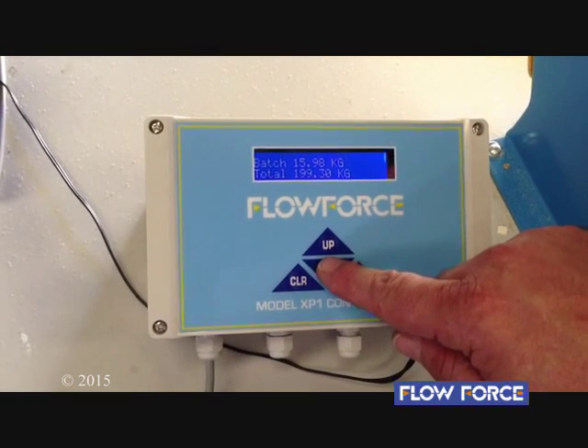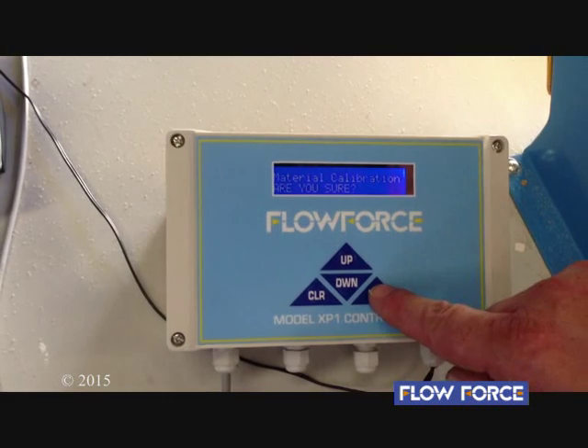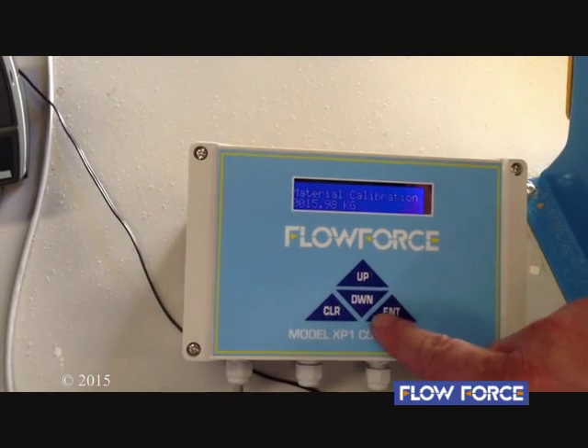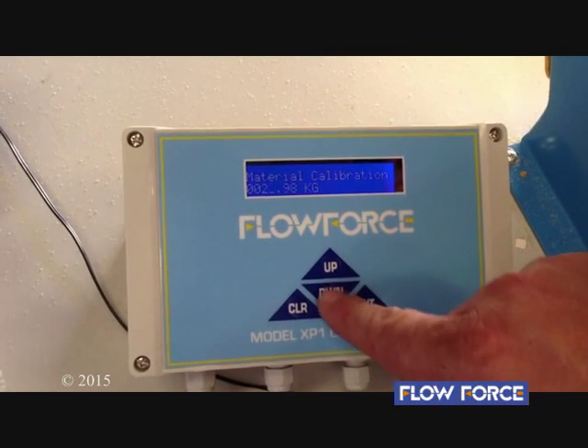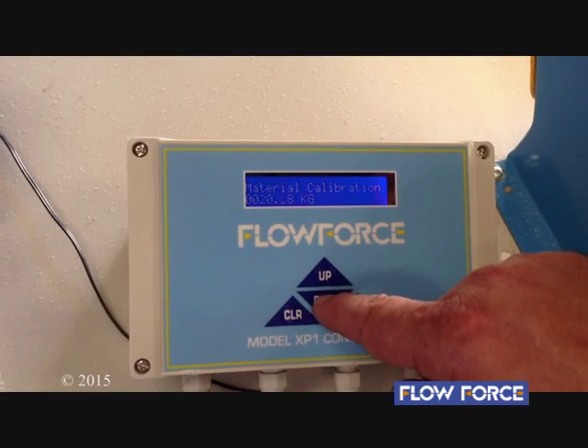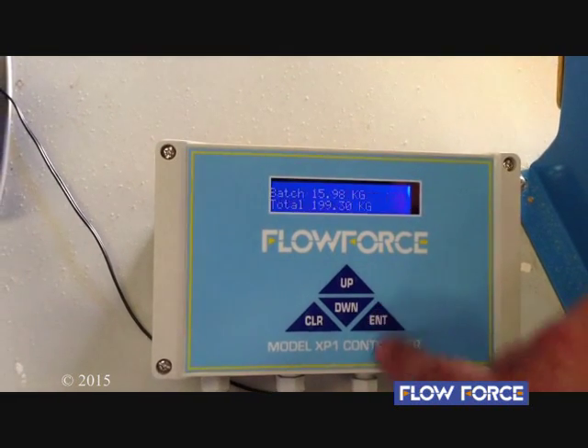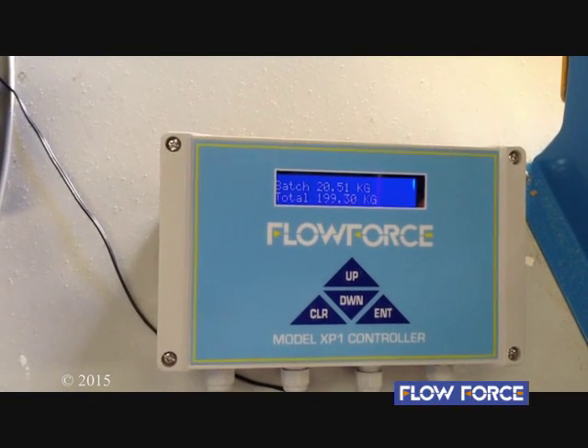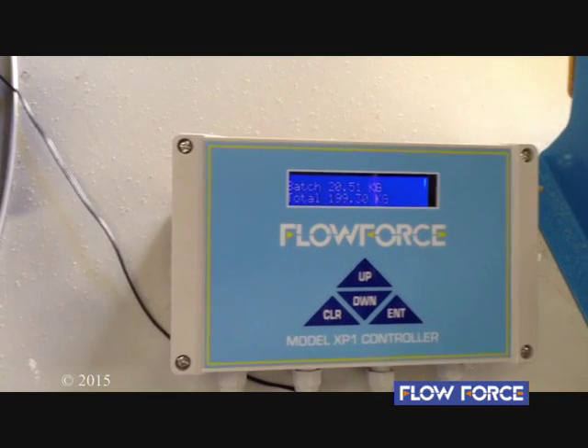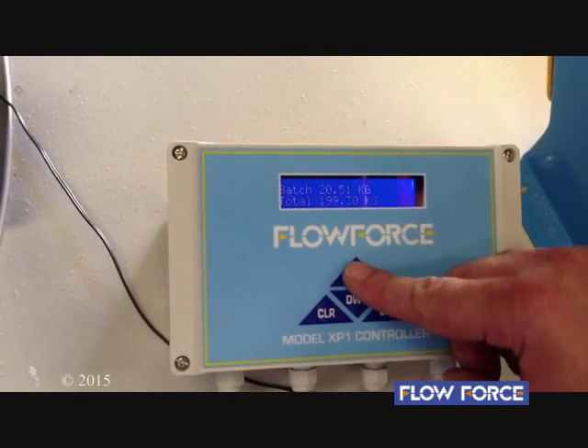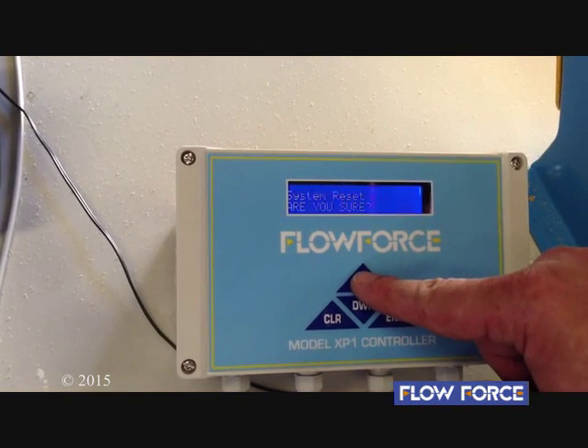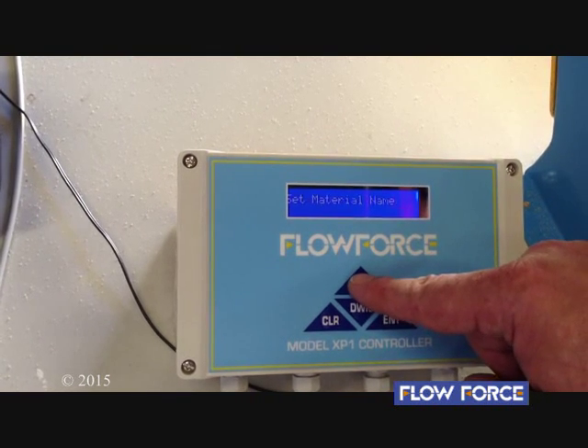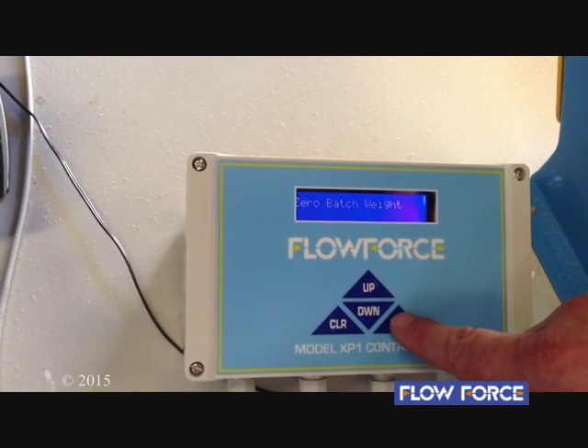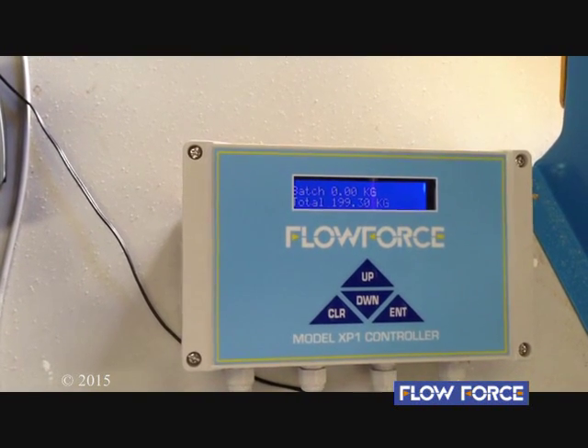So we go to the XP1 controller, using the up and down arrow buttons, we go to select material calibration, enter, and then we scroll through the keys and we put in our actual weight, which is 20.2 kilograms. So now we've done the first test, and we can zero the batch weight and get ready to do our next calibration run. Zero batch weight, and we're now ready to run test number 2.